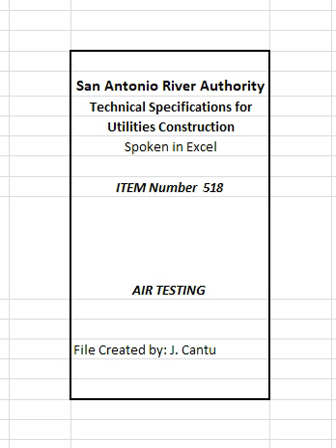Pipe sizes 36 inches inside diameter and larger shall be joint tested. Pipes under 36 inches inside diameter may be joint tested with the approval of the engineer. Maximum time allowable for the pressure to drop shall be 20 seconds regardless of pipe size.